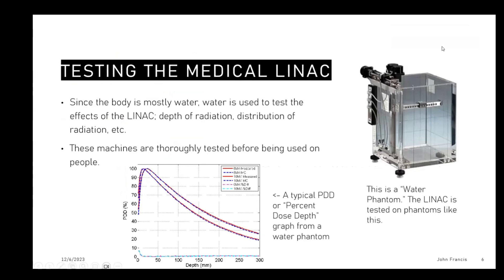They test the medical LINAC regularly at a hospital — probably at least twice a week just to make sure it's working properly. To test medical LINACs, they use a water phantom. This is a picture of a water phantom here on the right. The reason they use water is because our bodies are mainly made up of water. They'll generate a PDD graph, which stands for Percent Dose Depth — a normalized graph showing how much radiation penetrated how deep into the patient. It's a one-dimensional test where they shoot the beam at the water and measure how deep it goes.